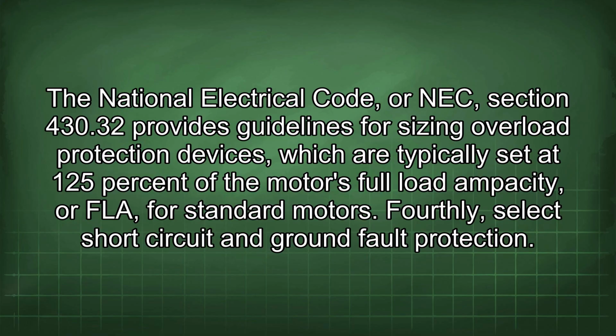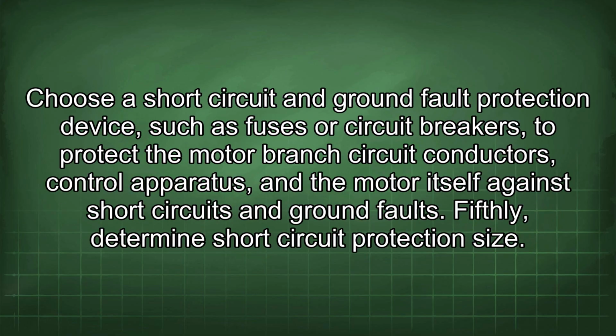Fourthly, select short circuit and ground fault protection. Choose a short circuit and ground fault protection device, such as fuses or circuit breakers, to protect the motor branch circuit conductors, control apparatus, and the motor itself against short circuits and ground faults.